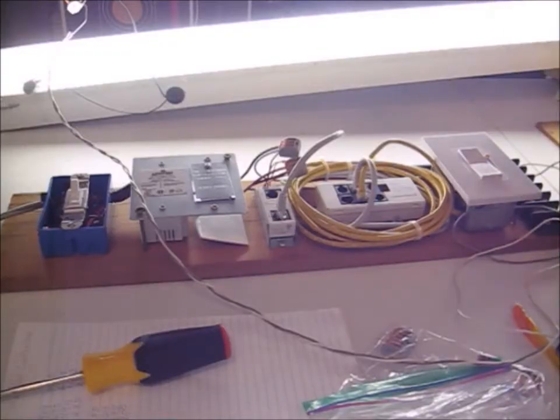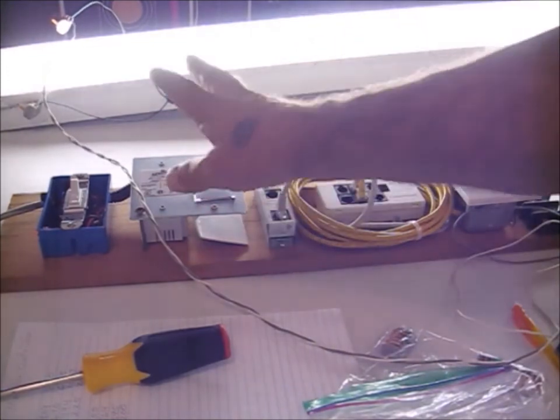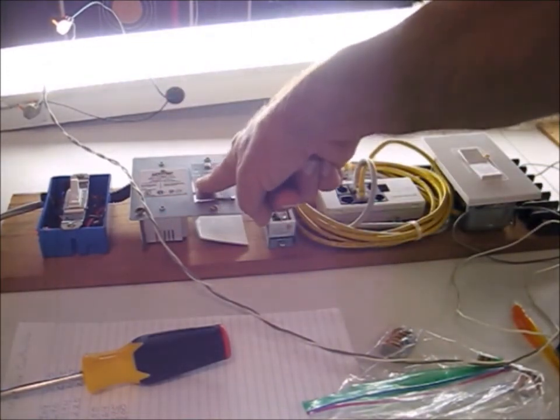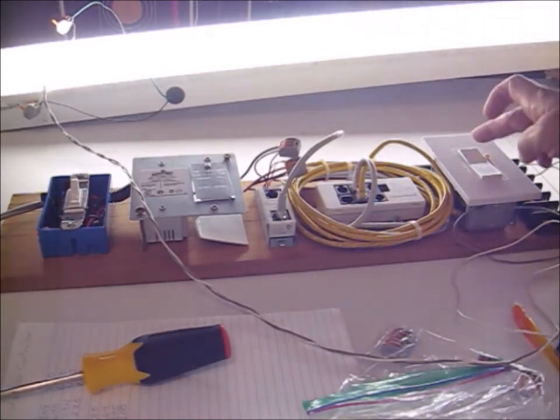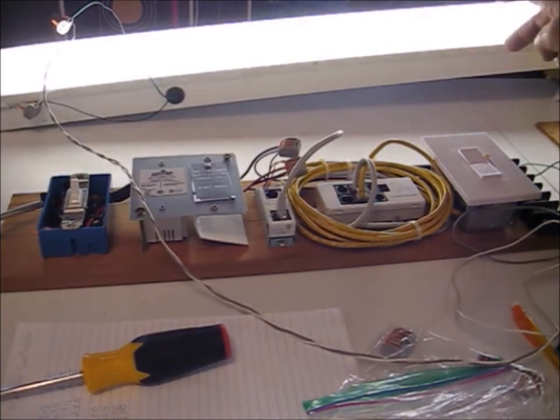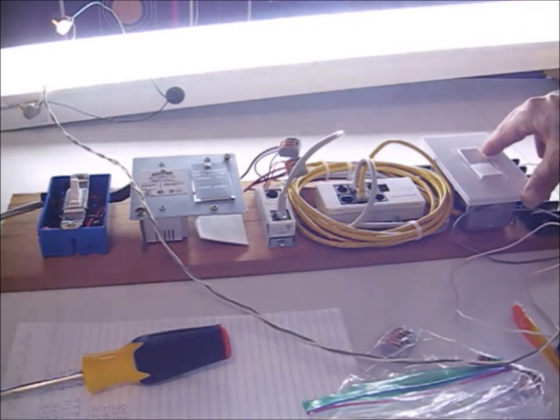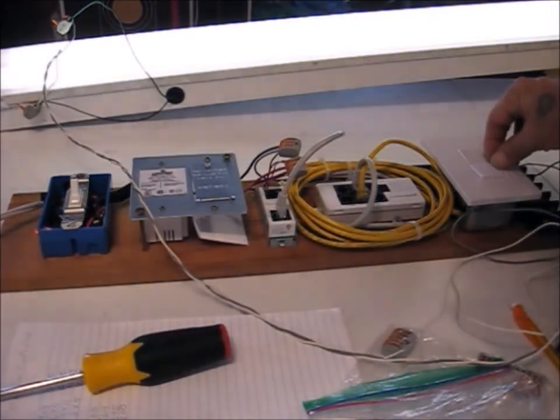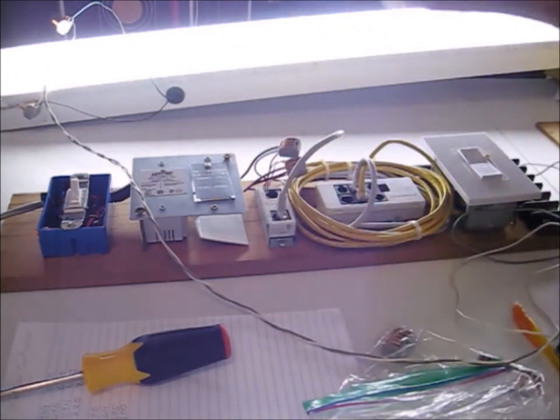Now after making sure it's safe to connect to this EcoSystem ballast, I'm powering it off the bus supply on the test set. The question is, does it respond to standard short address DALI signals? And I am pretty sure you can see, probably even on the camera, that it certainly does, including the continuous dimming command. So there you have it. Let's get a light meter out and take some readings.